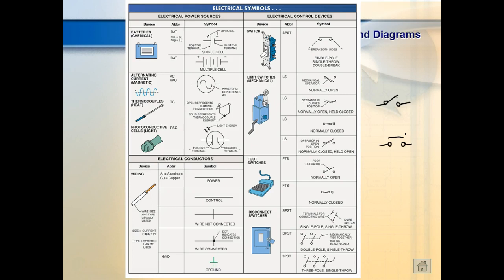One of the problems we have in industry every once in a while is a contact welds together. Every time a switch closes it creates an arc, and every time it breaks it creates an arc. Those arcs are 32,000 degrees. So we try to break fast and bring the contacts together fast because that helps extinguish the arc. But sometimes the contact actually gets welded over to the other side, what we call a welded contact.